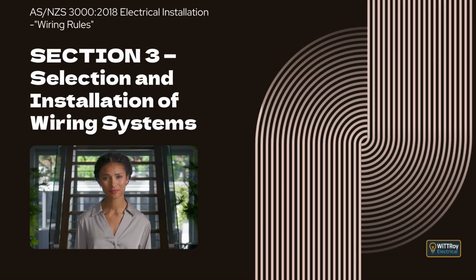Clause 3.10, Enclosure of cables. This clause explains when cables must be enclosed, what types of enclosures are acceptable, and how those enclosures must be installed so that cables are protected from damage and remain safe throughout their service life. Clause 3.10.1, General. This clause explains that some types of cables must be enclosed to provide mechanical protection, electrical safety, and durability, depending on how and where the cable is installed.